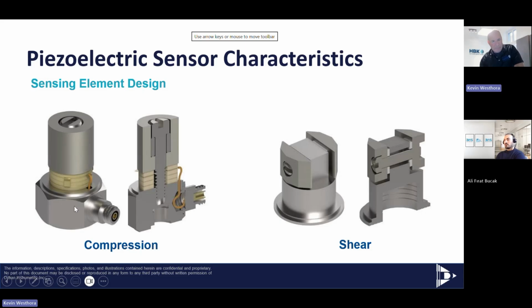So we have a titanium base, we have a stack of crystals. Looks like we have 4 crystals on this accelerometer that are stacked together, and then we sum the output of those 4 crystals. And then this big silver thing on top is actually kind of green, but it doesn't show it there in the picture. But this thing is called the seismic mass, and this is made out of tungsten. And then we preload the entire stack together with this screw.